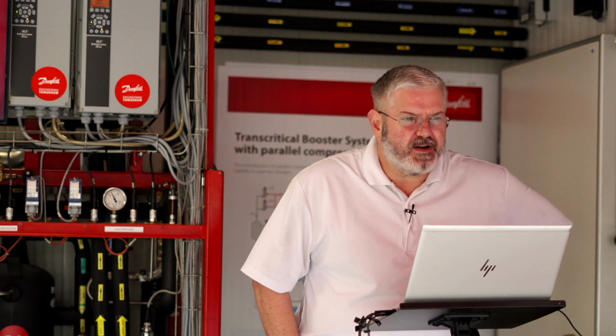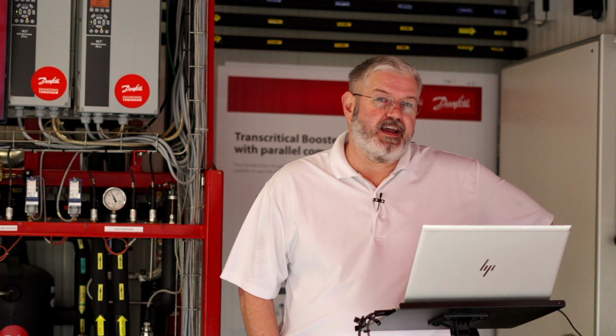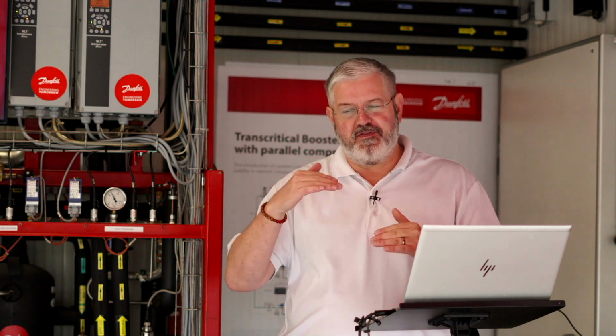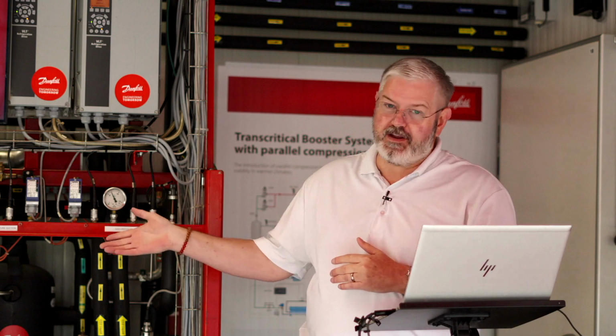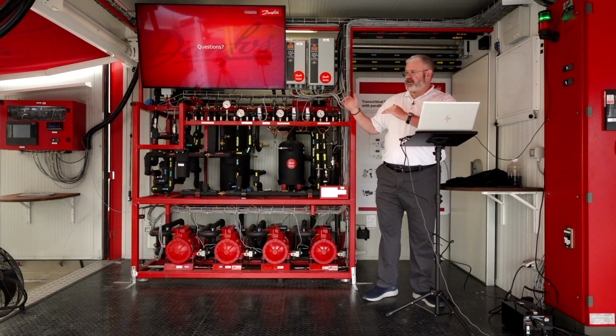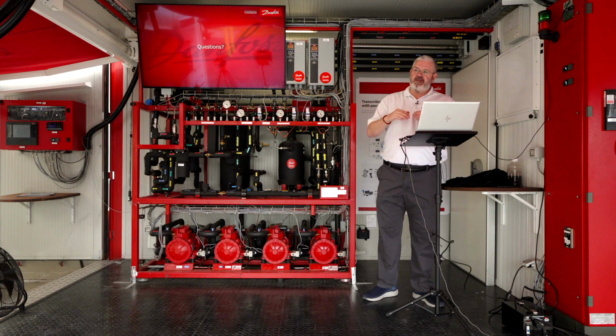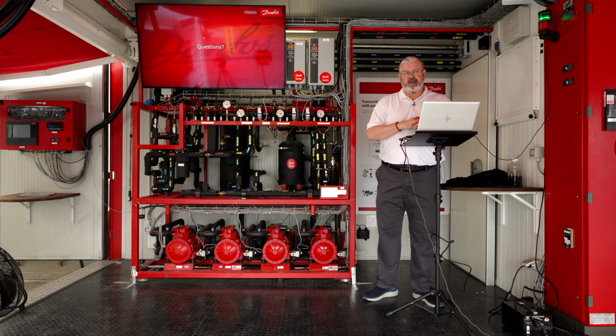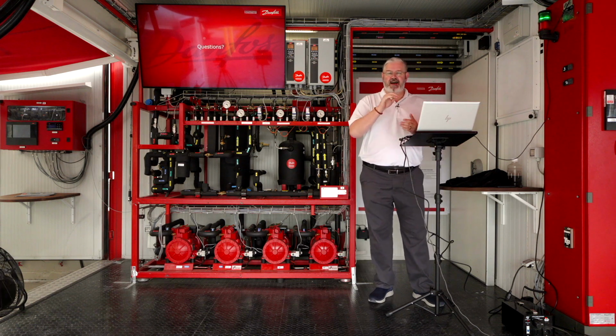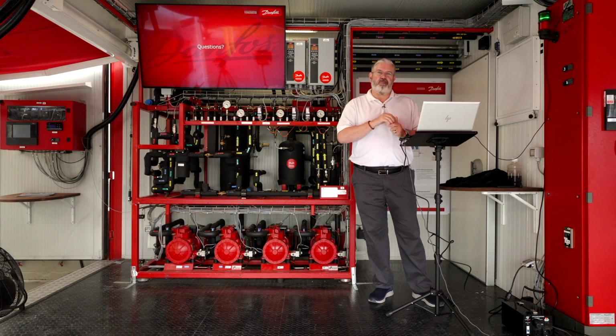So our next question is, how are the users controlling the high pressure valve as a backup when the ejector block is utilized? I'm going to be honest with you, I haven't dug into that. It just came to light recently that most people put in both valves. I've seen on this particular unit it doing what I described earlier, in cooler ambients it's kind of taken over with the high pressure valve. And then at a certain point, the honest answer is we've got settings that determine that. But if I tried to tell you what they were at this moment, I'd be giving you a hip shot, which I don't want to do. I'm going to respond to all of these questions, and I'll put a better answer in it for you.